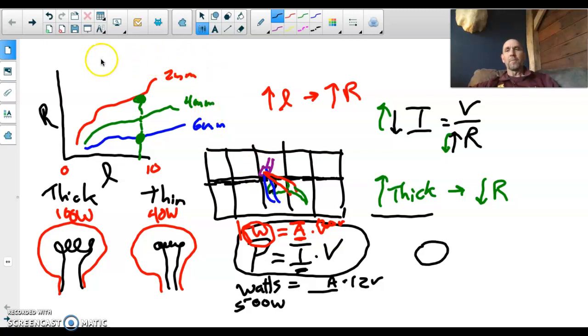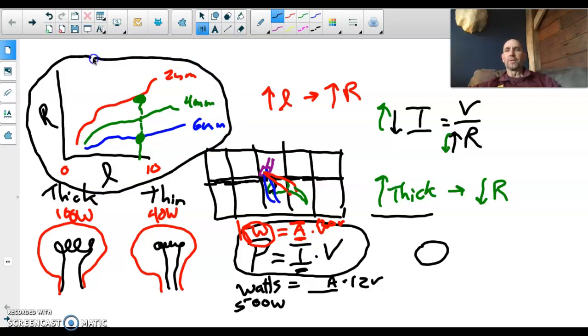So coming back to this lab, this is called the Lead Lines Lab. It's a very simple, crude lab, crude in the sense that there's very little equipment to it. It's just that index card and a multimeter that we use to measure the resistance. When we're measuring resistance with a multimeter, we call it an ohm meter. You could call it a resistance meter, but resistance is measured in ohms, right? The symbol is omega. So then we call it an ohm meter.